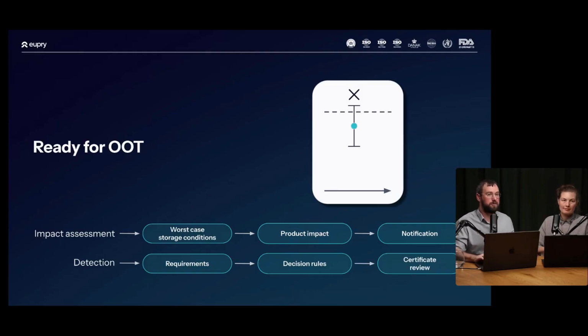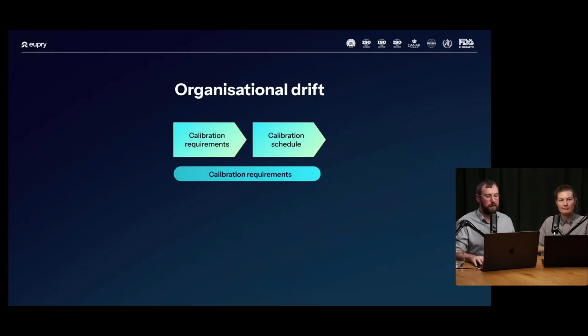And again, back to the certificate review. Just going a little bit further, and then we'll go through all the great questions here. The last thing we often see is what we call organizational drift. Let's say on an organizational level, you put in a lot of effort in defining your calibration requirements and your calibration schedule, all combined in these calibration requirements.